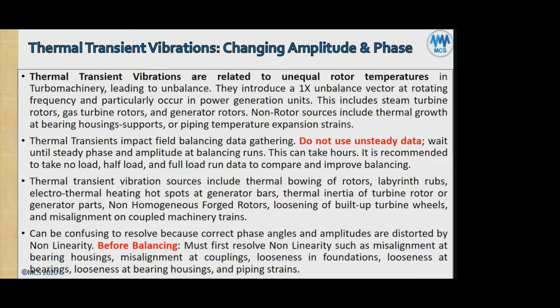So therefore, as you can see, especially for generators, you definitely want to run as close as you can to full load. However, it's good to also take no load, because you want to compare at a constant speed, for example 3,600 RPM, which is the synchronous speed at 60 hertz. You want to take the no load to see what is the normal unbalance vector on the rotor. And then when you go to full load, you want to see what's the thermal unbalance vector, which is additive to the normal balance vector.